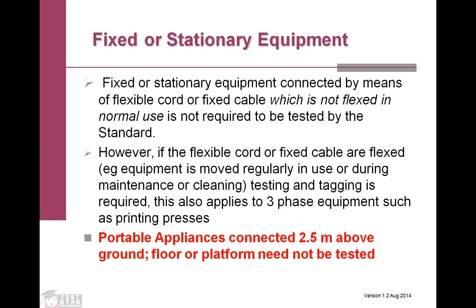We take people through those processes, and it's quite possible, particularly with modifications to machinery where earthing is involved. If your electrician's adding an extra part to the machine, testing and tagging can be an important part of that process once it's done, to make sure the earthing system is working effectively. Even though those big presses don't get moved, picked up, or flexed in normal use, testing and tagging is still worth considering as a good safety mechanism.